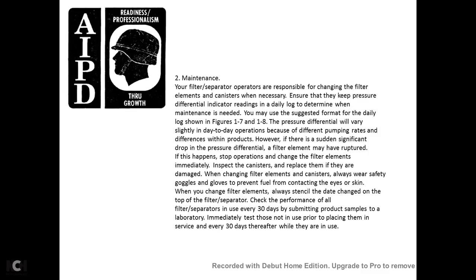You may use the suggested format for the daily log shown in figures 1.7 and 1.8. The pressure differential varies slightly in day-to-day operation because of the different pumping rates and differences between the products. However, if there is a sudden significant drop in the pressure differential, the filter element may be ruptured. If this happens, stop the operation, change the filter elements immediately, inspect the canister, and replace damaged parts as needed. Always wear safety gloves to prevent the fuel from contacting eyes or skin when changing the filter elements. Always stencil the date of the change on the top of the filter separator.